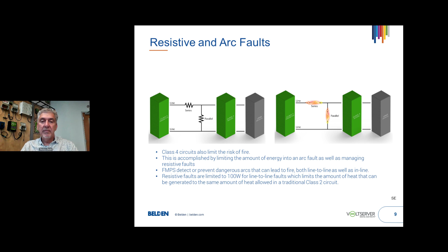Here's an overview of the faults that we're talking about and what has been done conventionally up to date with electrical distribution and what fault managed power does. So you could see in conventional, let's take an AC final distribution circuit, like a 110 volt circuit in your home. You can obtain line to earth, ground fault, or arc fault, right? Line to line is very problematic. Usually ground fault detectors are going from a line conductor to earth, and arc fault is also very difficult to detect line to line. It takes a long time to develop. By the time you're detecting arc fault in a line to line condition, it's already carbonized. Series arc is available with arc fault detection in parallel.